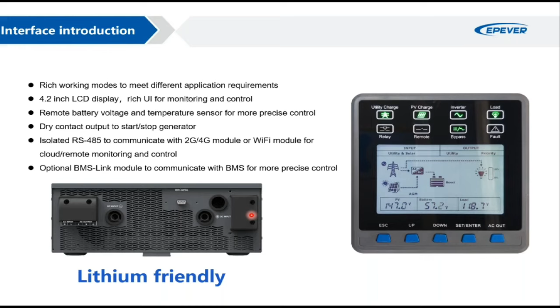Okay, what you can understand from the name of the product. UP is actually the name of the series, and H stands for the high series. And this is the power of the product. And then M here stands for PV tracking technology, which is in this case the MPPT tracking. These two numbers are the battery charging current and the battery voltage. So in this case, we have 80 amperes of charging capacity for the battery, and we have the 48 volt system because 4 stands for 48 and 2 stands for 24.